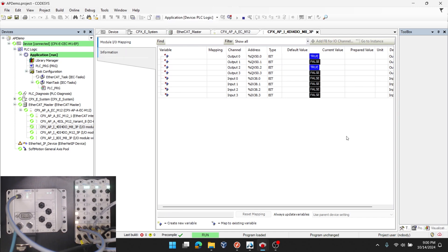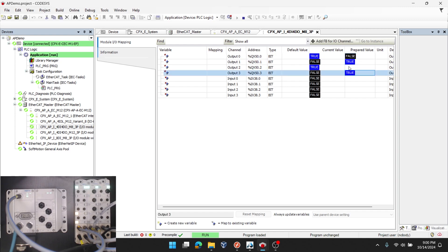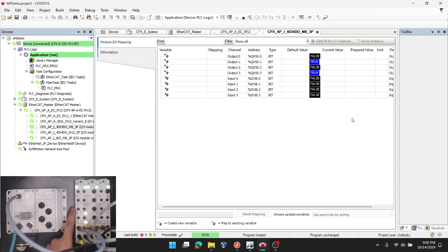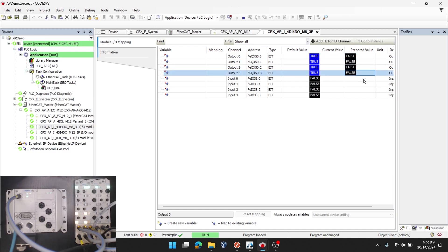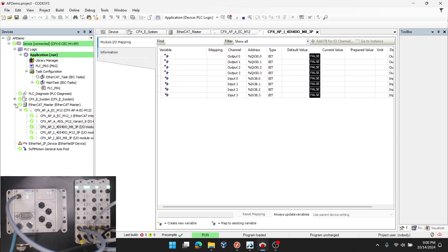Now I can force those on and you see two lights came on. I'll switch those. And it switches from the left side to the right so you can see that the bottom of that module are my four digital outs and the top are my four digital in. I can turn them all on and then all off. Now you've verified that your CPXE rack system is up and running.